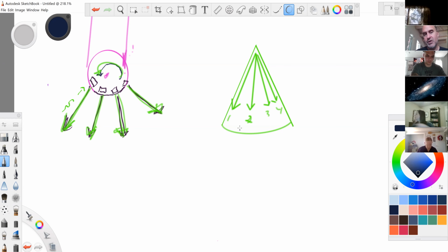One disadvantage is the distance between beams in the far field just keeps getting wider and wider and wider, whereas the distance between beams in the near field, they're very close. In fact, they probably overlap in the near field. So in the far field, there could literally be a small object that's not seen.